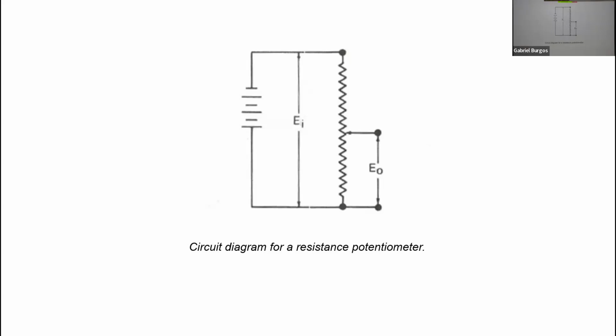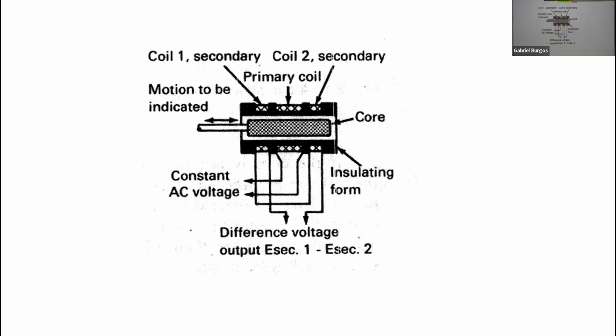Just a point. Okay, so now we'll go down to LVDTs: linear variable differential transformers. Notice the words secondary and primary. Here's the primary. You have three windings here, and then a ferromagnetic core. Now, people have built their own LVDTs using a nail for the core, or a piece of steel rod. But the cores of commercial LVDTs are actually high permeability materials, usually about 50% nickel and 50% iron, or thereabouts. These things get hooked up in a differential manner.